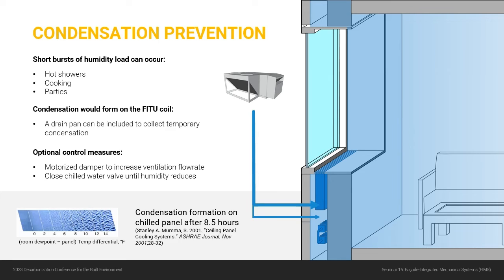But it is also important to note, I have this reference on the bottom of the slide. It shows that even if your chilled water were to be, say, 6 to 8 degrees below your dew point, which is really losing quite a bit of control over your humidity, even then, after 8.5 hours, you're only barely starting to form droplets. So it's actually not that easy to form these condensation droplets. So in most cases, it really shouldn't be a major concern. But there are things you could do to help prevent it from happening.